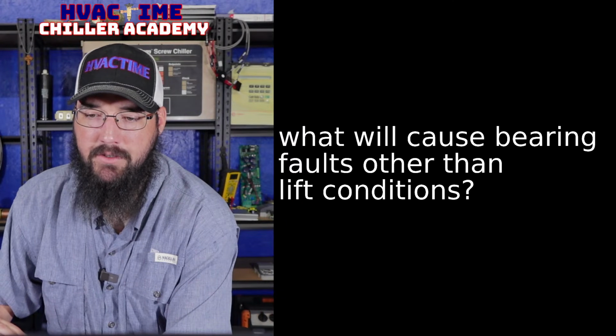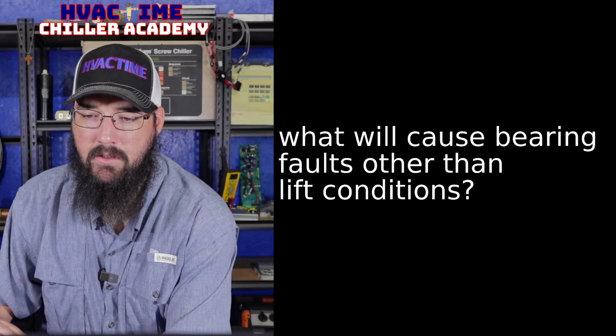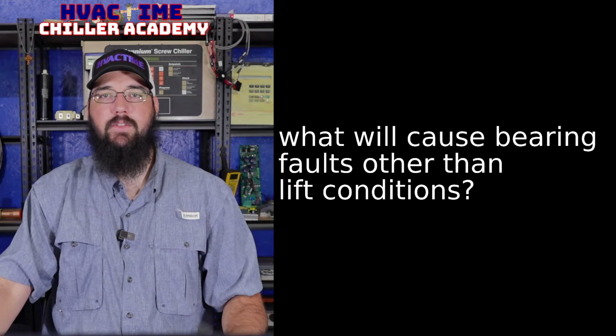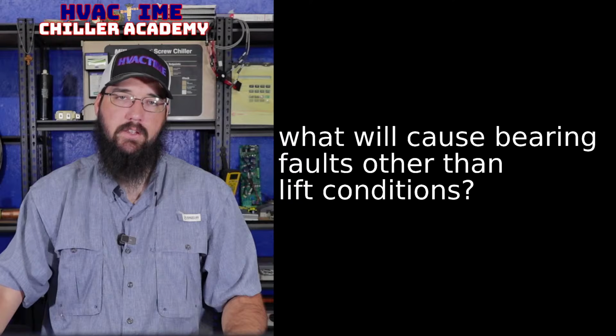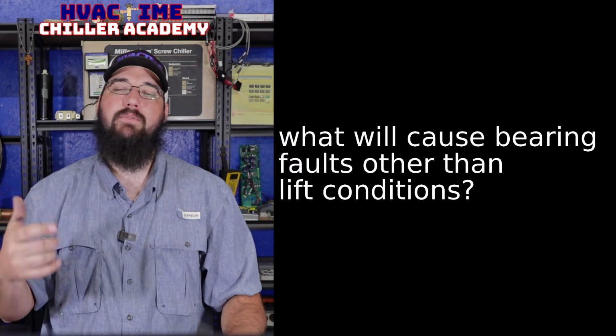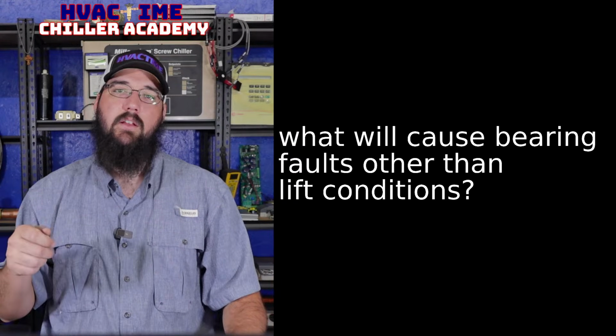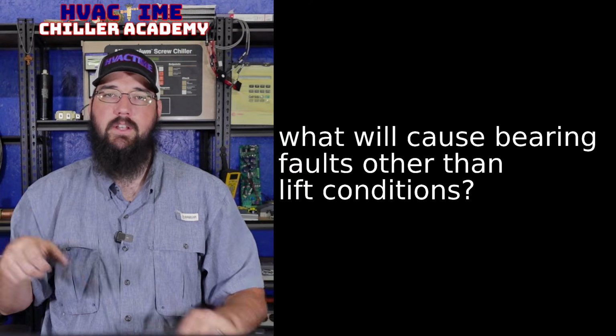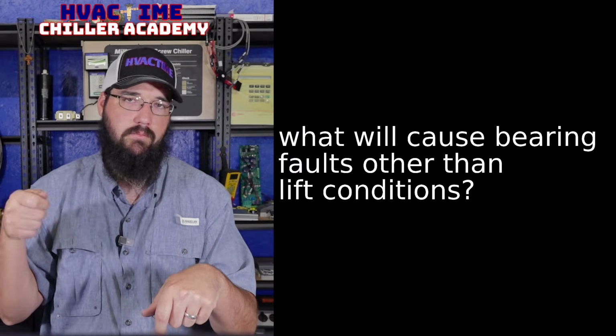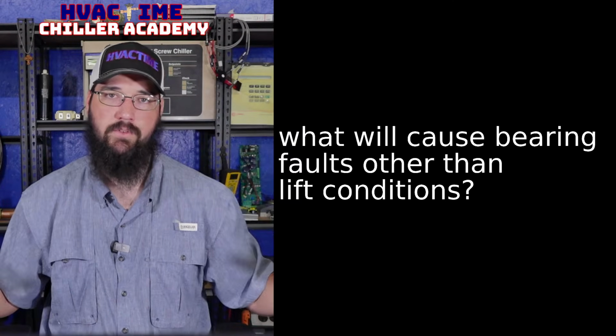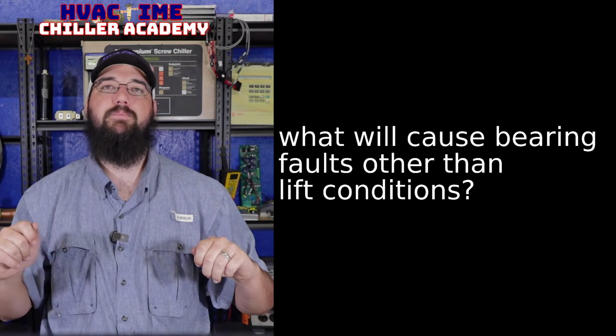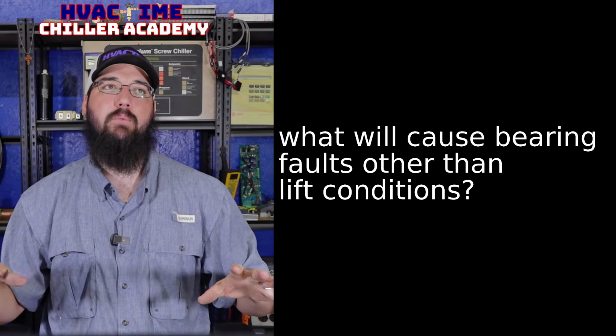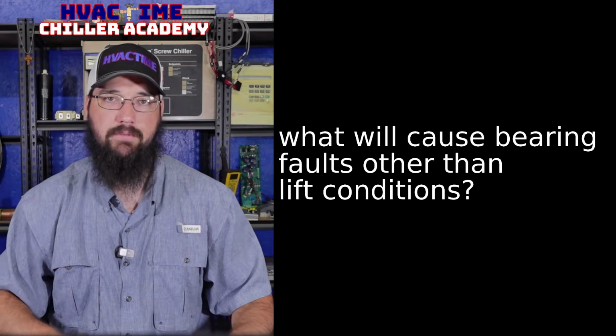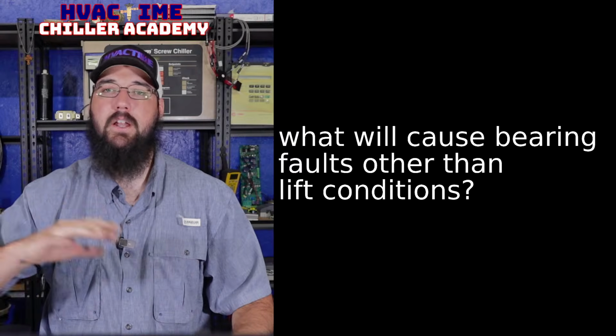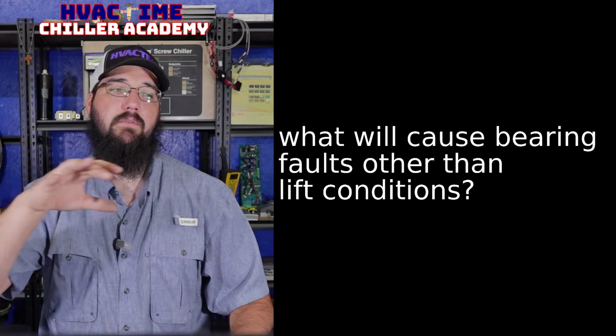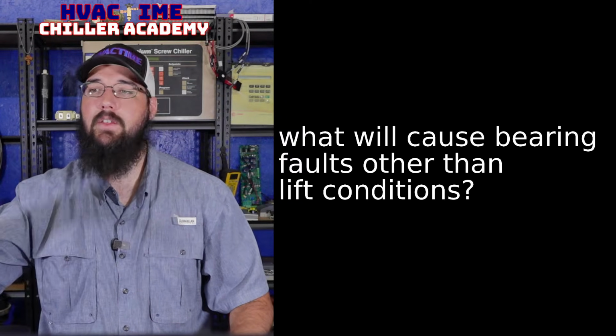I don't get how you mess up the calibration on a Turbocor. Yeah, if you go to do a calibration check and then you save it and it was a bad calibration, there are all kinds of little things that can influence it, and this is just how I've been trained on this process. You're supposed to completely disconnect everything else from the IO module, unplug everything else from the module, so nothing is influencing this compressor. We want to put it through a calibration check. And you don't want to save the calibration from the factory cal unless you absolutely have to. But not everybody does that and they end up saving it. And then that calibration is a less good calibration and it just ends up throwing the whole thing out of whack.